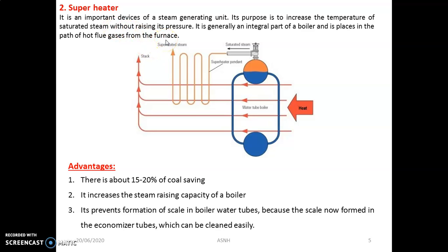The advantages of the superheater are: about 15 to 20 percent of coal is saved, so fuel consumption is reduced. Second, it increases the steam-raising capacity of the boiler. Third, it prevents the formation of scale in the boiler — some moisture remains in the steam, and the superheater converts that moisture into dry steam. Keep in mind that in the case of the superheater, we get maximum temperature rather than increasing the pressure. Pressure remains constant but the temperature of the steam increases.